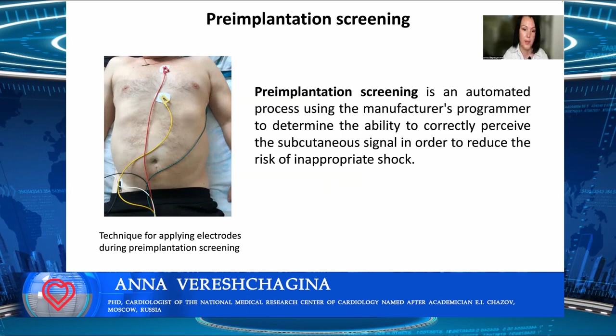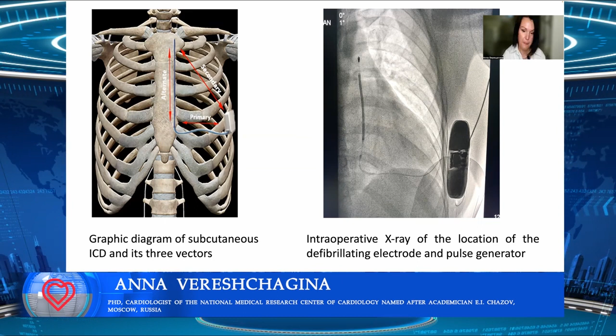Arrhythmia detection is carried out using all the three vector formats between the three sensing poles of the system. This consists of the primary, secondary, and alternative vectors. The pulse generator is placed in the area of the 5th to 6th intercostal space between the left anterior and middle axillary line. The device is large, compared with the transvenous ICD, weighing about twice as much, 145 grams.